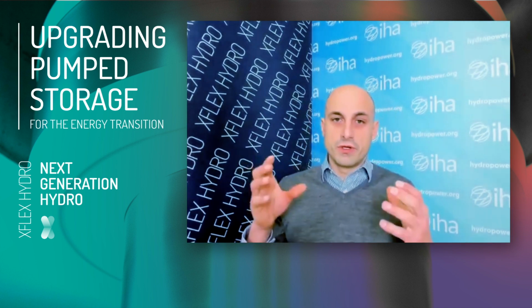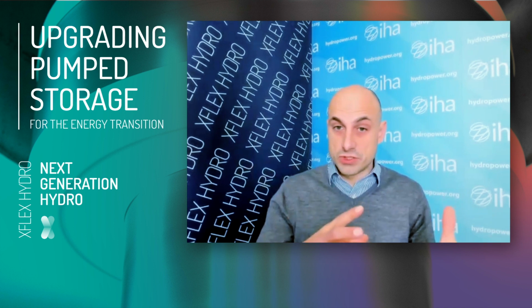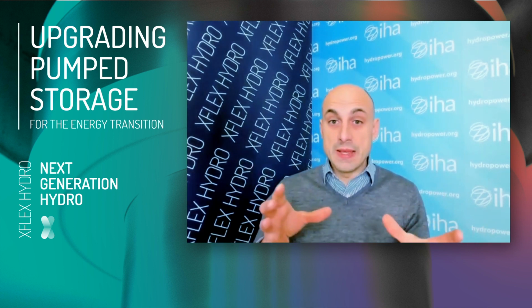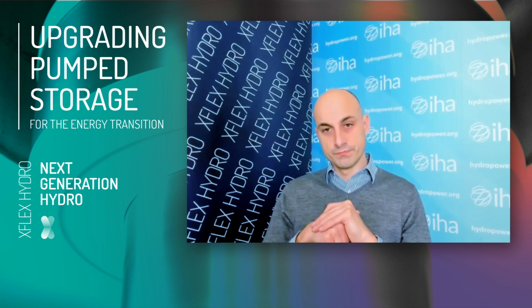Looking back at the two technologies discussed today, hydraulic short circuit and variable speed, which is capable of providing what, and which is more adapted to which type of service? For hydraulic short circuits, the main target is to address primary and secondary control by operating the turbine at the same time as the pump. For variable speed technology, you can address the classical primary, secondary and tertiary control, but on top of that, you can address fast response time and new services like fast frequency response or inertia emulation.